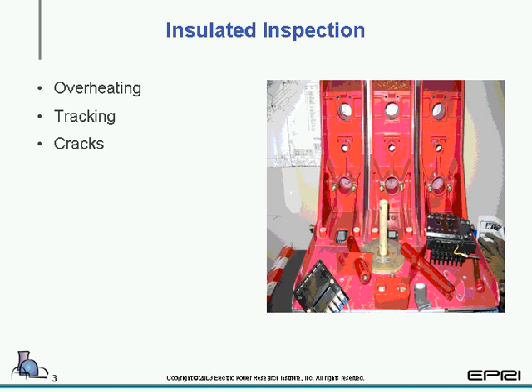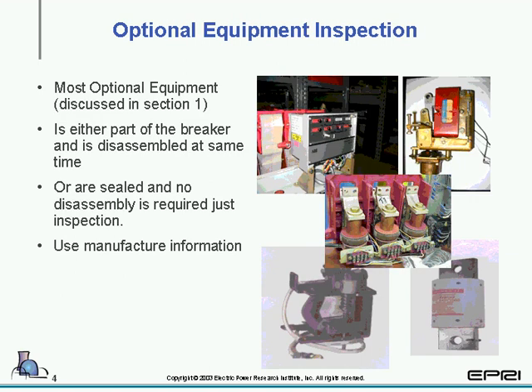Insulated parts. We're going to look for overheating, tracking, cracks, and as we spoke about, you're going to want to look where the hardware bolts into or through the insulated pieces. And you'll see that sometimes you can use a flashlight to inspect the parts. They'll show hairline cracks that can't otherwise be seen. Optional equipment inspections. Now in section 1 we spoke a lot about many different types of optional equipment. Use the instruction manuals provided by the manufacturer as well as common sense.